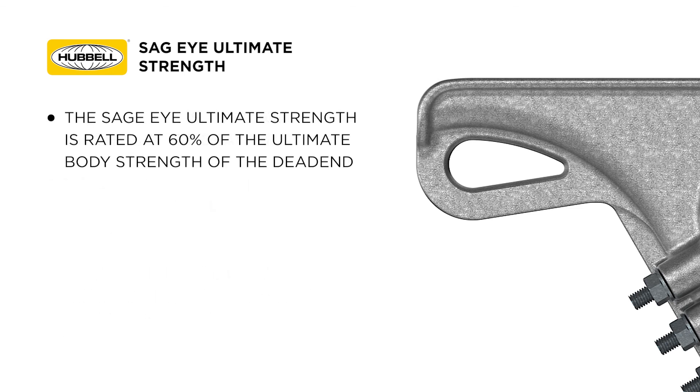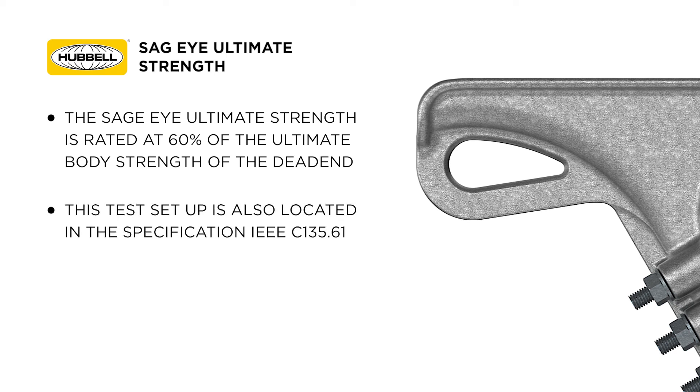The Sag Eye ultimate strength is rated at 60% of the ultimate body strength of the dead end. This test setup is also located in the specification IEEE C135.61.